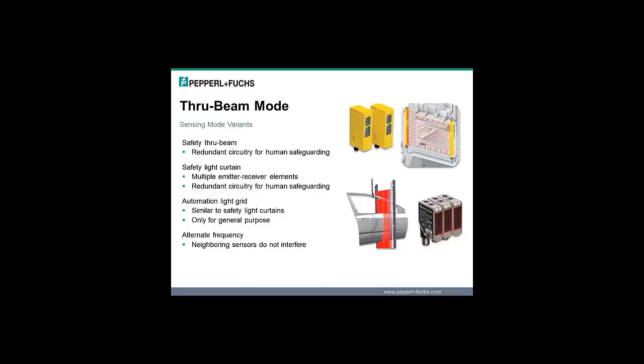Variants of through beam sensors include safety through beams which have redundant circuitry to meet the applicable criteria for human safeguarding, safety light curtains which have multiple emitter-receiver elements combined with redundant circuitry to meet the applicable criteria for human safeguarding, automation light grids that are similar to safety light curtains but only approved for general purpose applications, and alternate frequency models that ensure neighboring sensors do not interfere with each other.